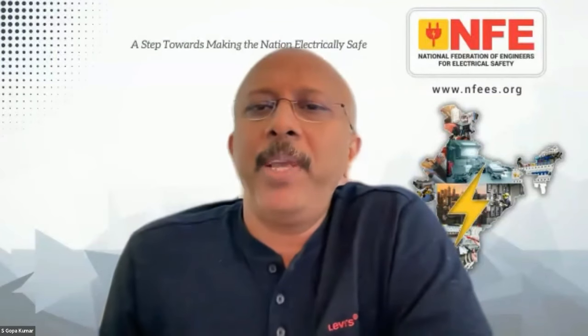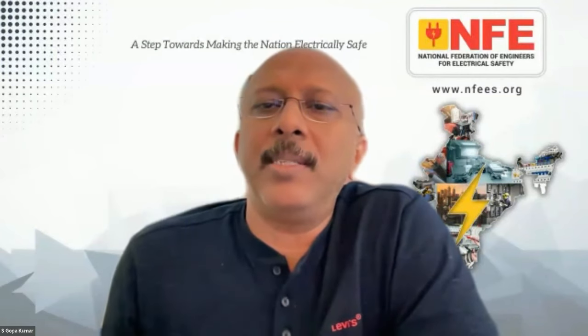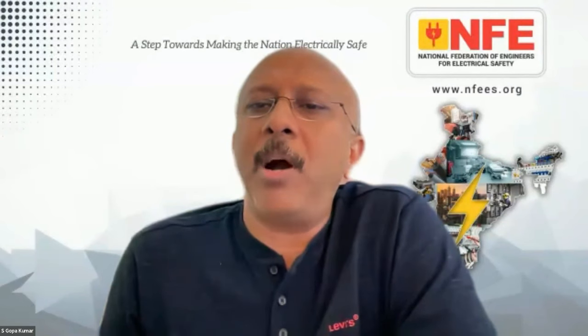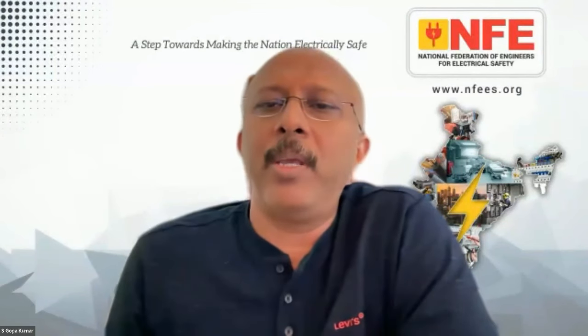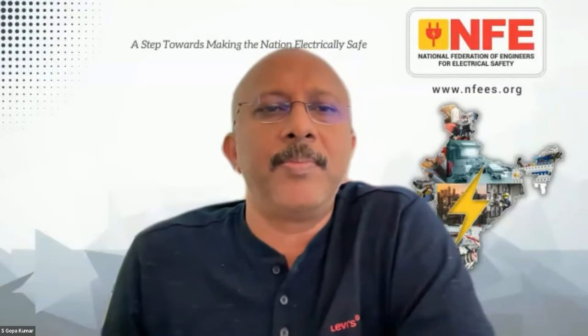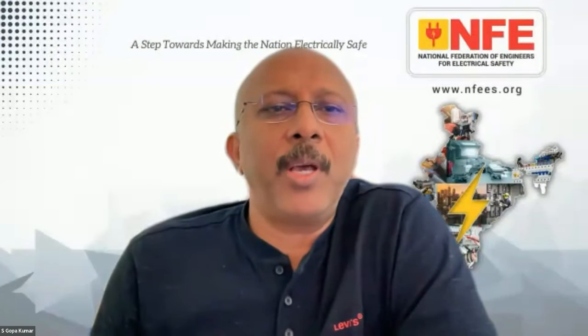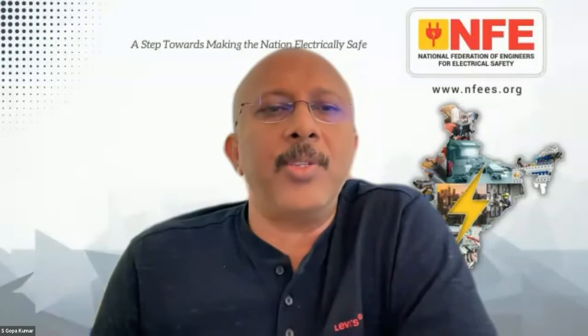So Mr. Paul, we have another question again from Mr. Sanjay. Generally, in a healthy earthing system, how much leakage is maximum allowed in the earth conductor? Sorry, say that again. What is the maximum allowed earth current, the continuous current through the earthing conductors or through the protective conductors? Ah, right, leakage. Okay, yeah.